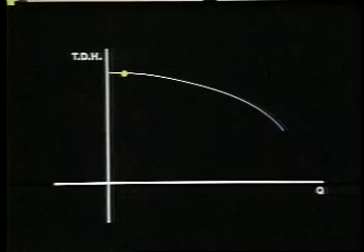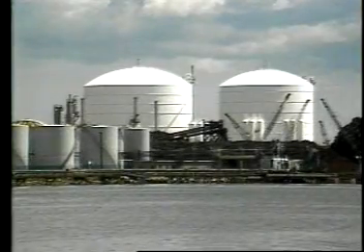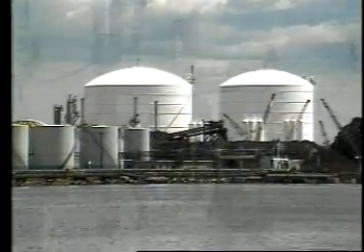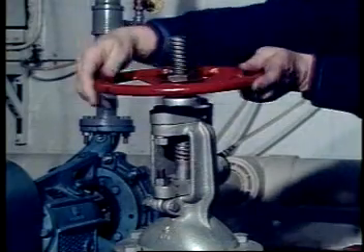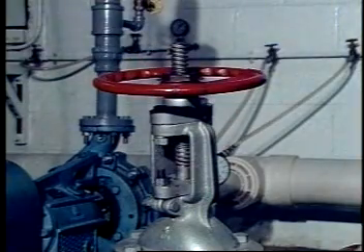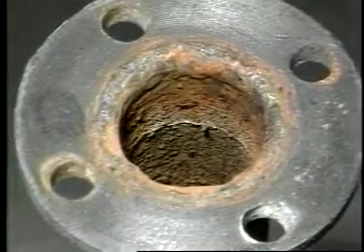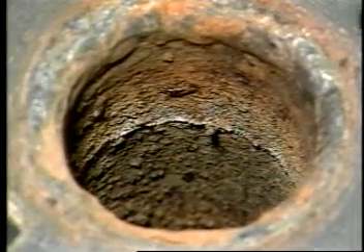Operating at zero capacity is called operating at shutoff. At this point, no liquid leaves the pump and the water churns around in the casing, with all the energy being transferred into heat. The variation of liquid levels in tanks is a normal operating condition that must be dealt with by the pump on a daily basis. The variation of friction losses is also fairly normal. This can occur from the throttling of a valve in the discharge side of the system, either manually or by automatic control, or from the gradual buildup of corrosive or other deposits in the bore of the pipe, in heat exchangers, or in filters.